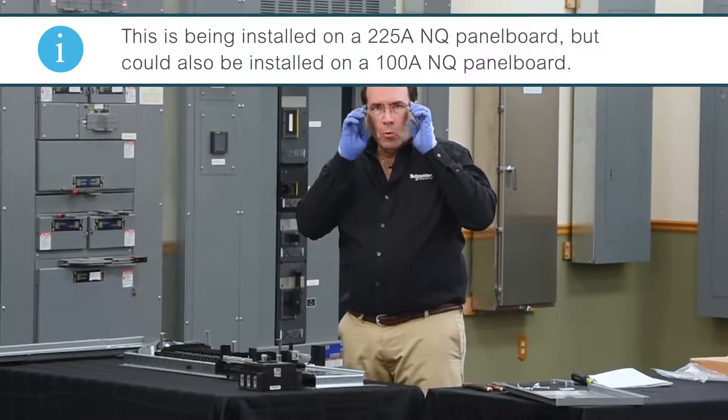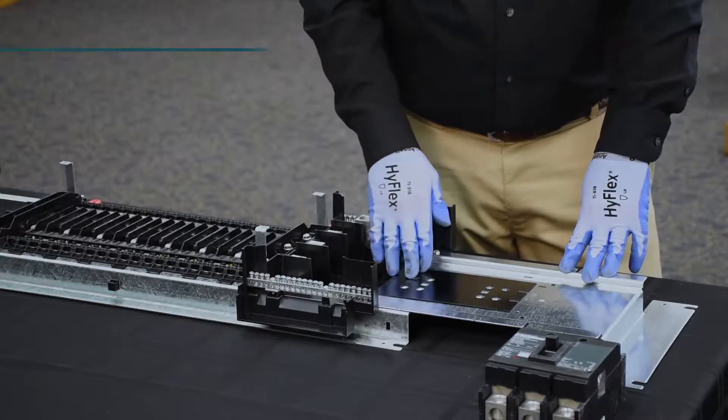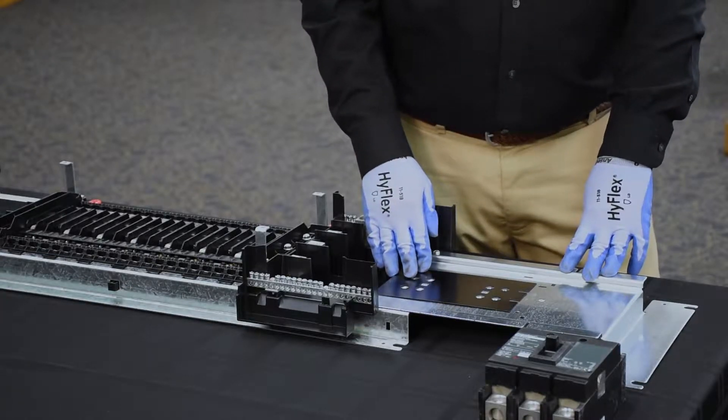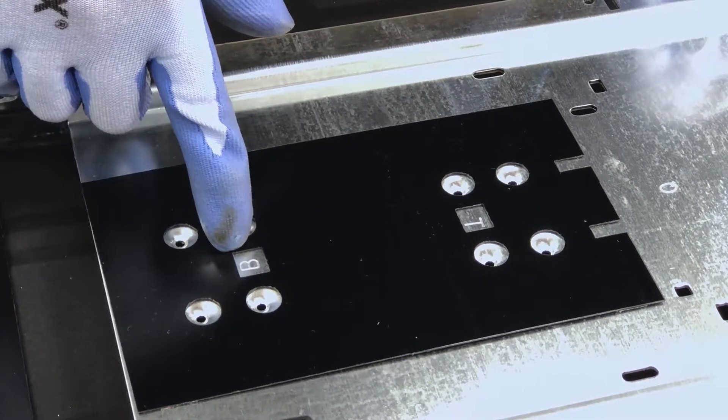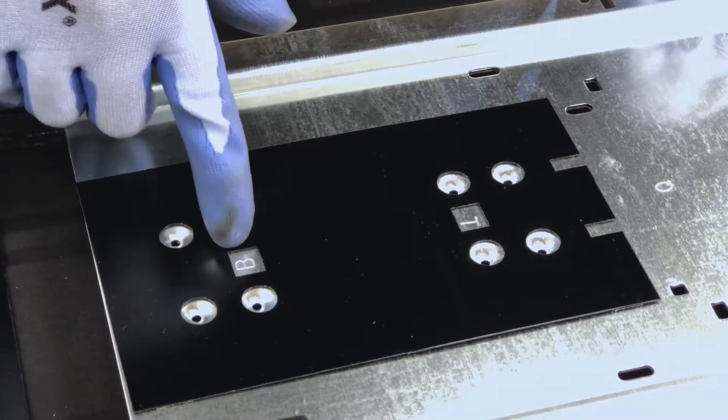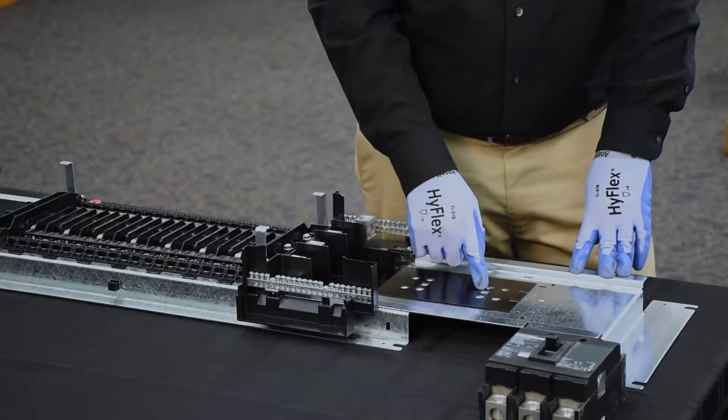Next, we'll position the breaker onto the mounting pan based on feed direction. The mounting pan has eight holes, two sets of four. There's a B mark for bottom feed for the set of holes to be used for bottom feed, and there's a T mark for top feed for the holes to be used for top feed.